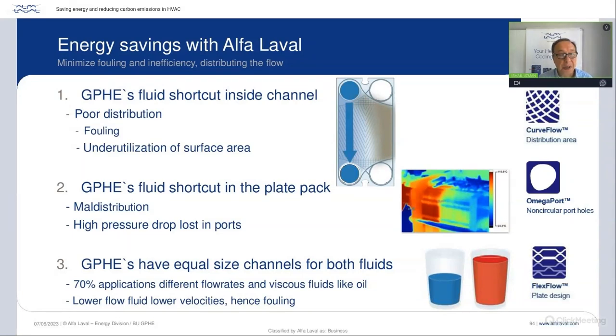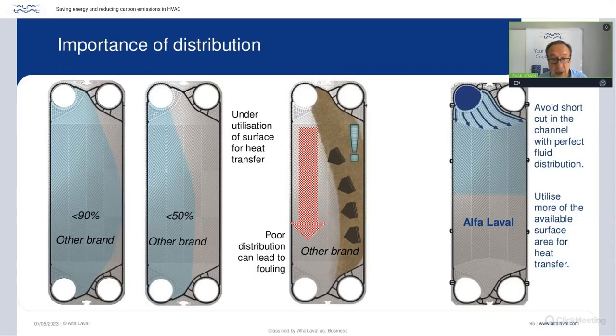Usually the lower flow, because the channel sizes in a plate heat exchanger, and this is all manufacturers, and also before it was rather, the channel sizes are usually equal. And when they're equal, the lower flow rate will have faster fouling because of lower channel velocity. So these three features help to reduce fouling, they help to save energy and optimize the use of your pump energy for better heat transfer.